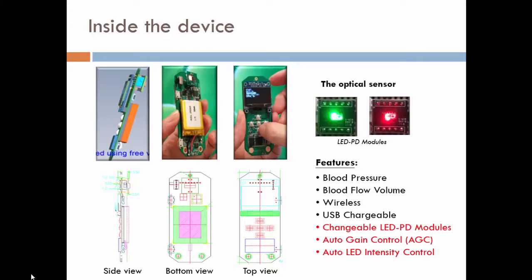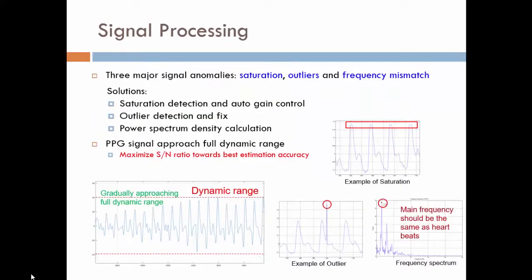So here are the LED and PD module. Several very important features we have implemented: the LED and PD module is actually changeable for different wavelengths, and the PGA inside has the functionality of AGC auto-gain control. And also we will based on the quality of the PPG signal online tune the LED emission intensity in order to take care of different skin colors.